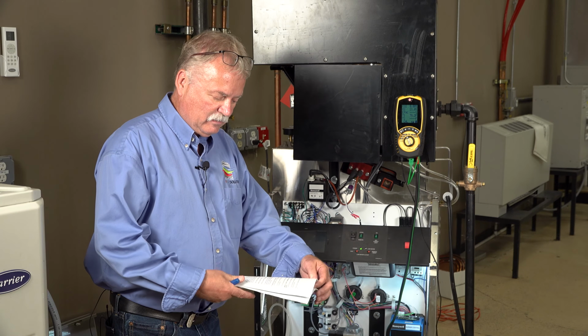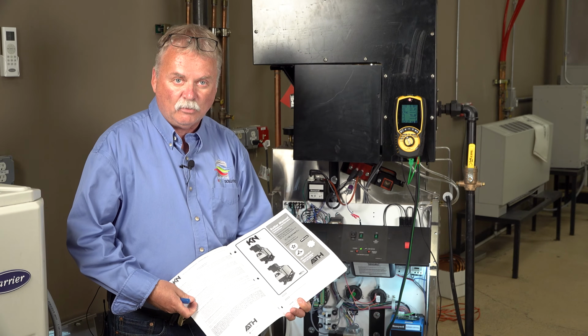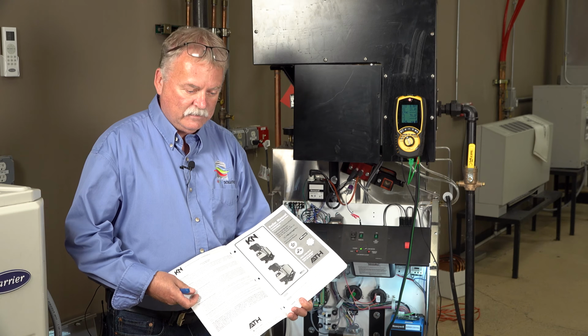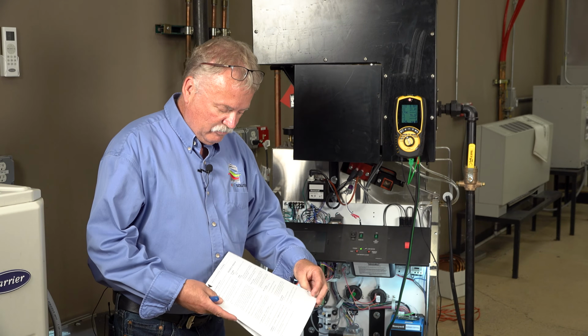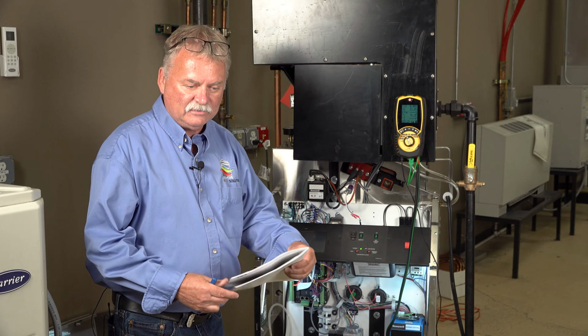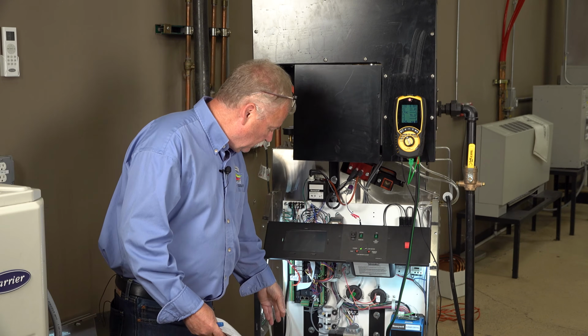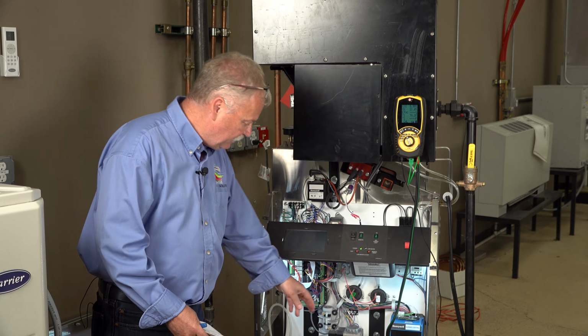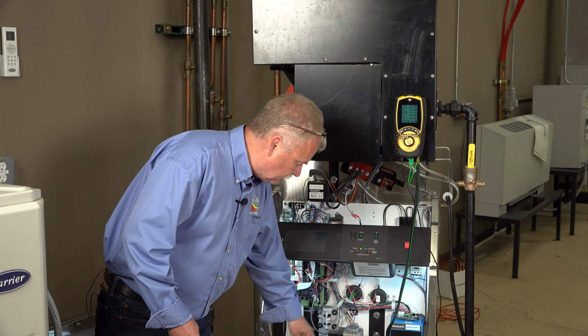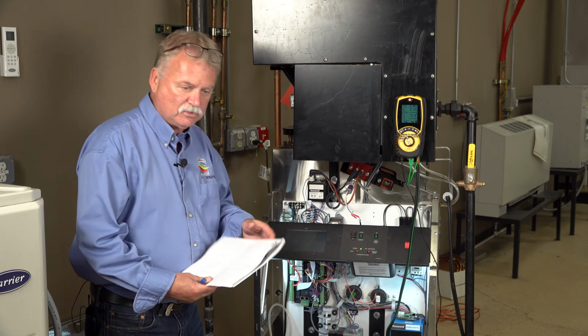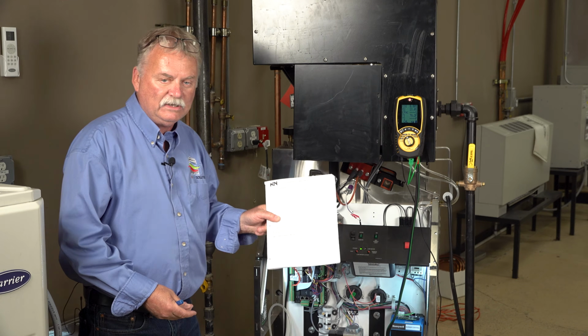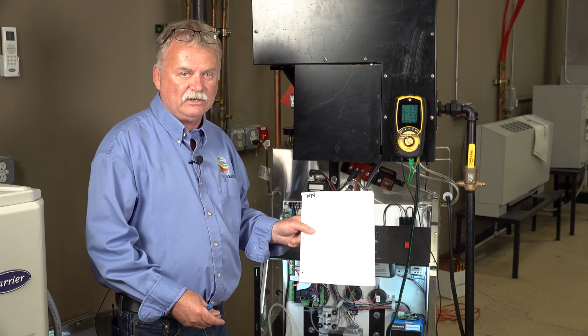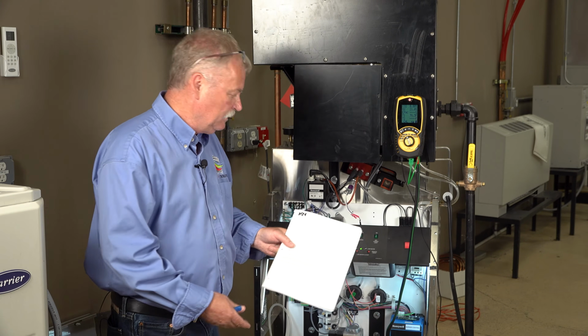Before you touch anything, you want to make sure you have the manual from the boiler itself. In the manual, you'll find all kinds of information. You'll find where the gas test port is. You'll find the high adjustment feature. You'll find the low adjustment feature. It's all listed in the manual. So please make sure you have a manual before you start doing a combustion test.